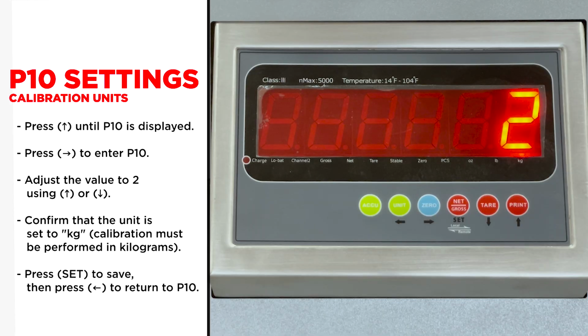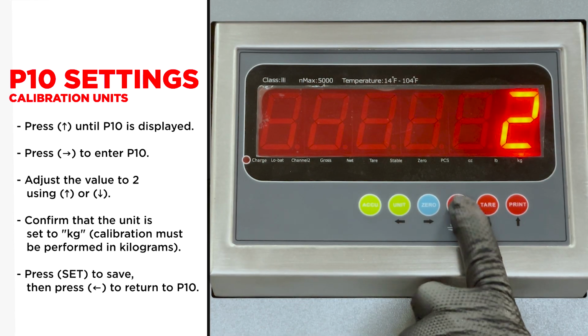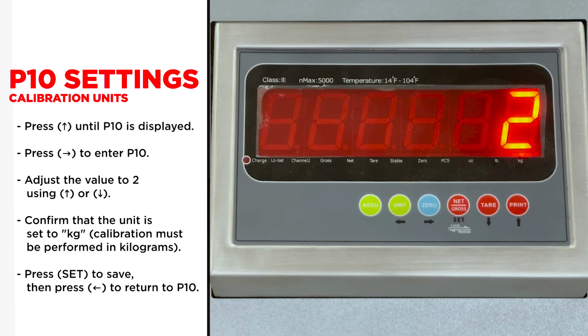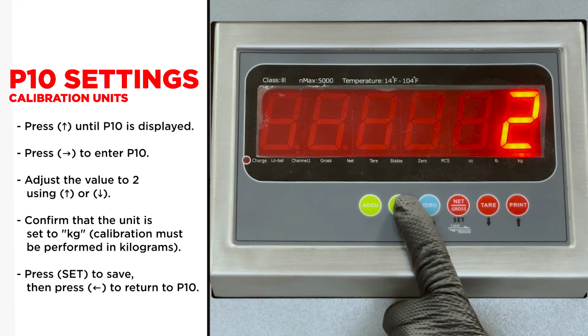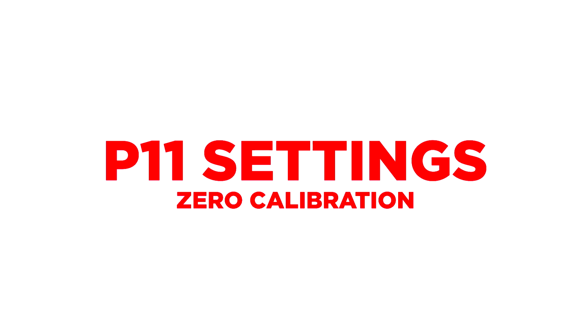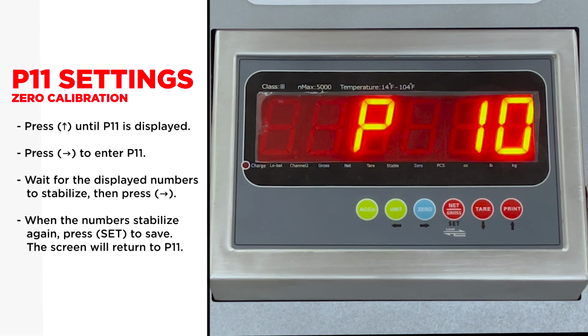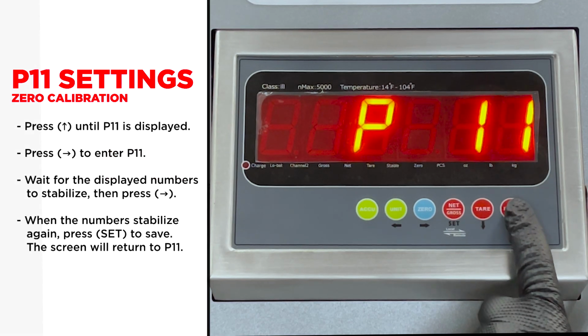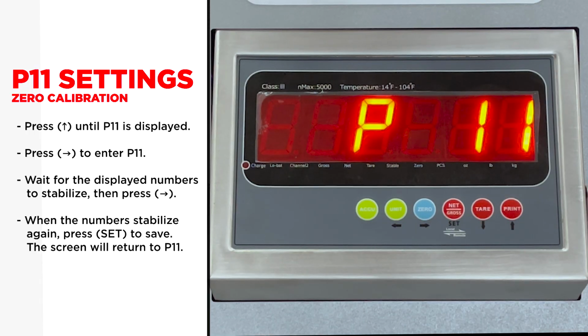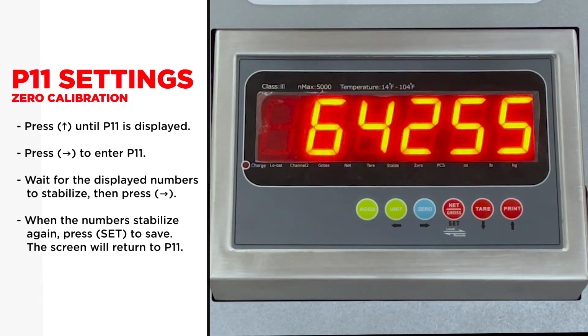And at this moment, it will show the units as kilograms. Calibration needs to be done in kilograms and not pounds. Now press set to save. And now press the left arrow to go back to P10 settings. Now press the up arrow to turn to P11. Press the right arrow to enter P11 settings.